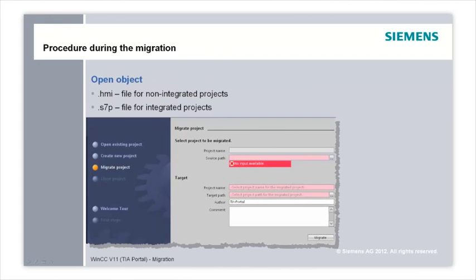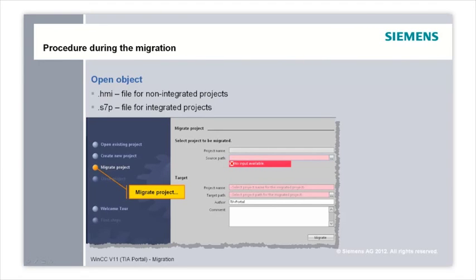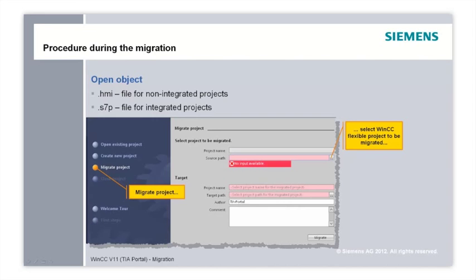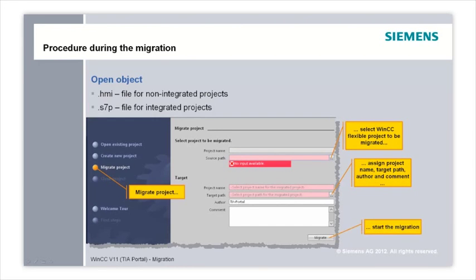How to realize a migration: you can migrate WinCC flexible standalone projects to WinCC version 11 as well as WinCC flexible projects integrated in Step 7. In the WinCC version 11 portal, you choose the action 'Migrate project', then you specify the source path of the Step 7 or WinCC flexible project as well as the target path for the migrated project. Press the Migrate button to migrate the project to WinCC version 11.